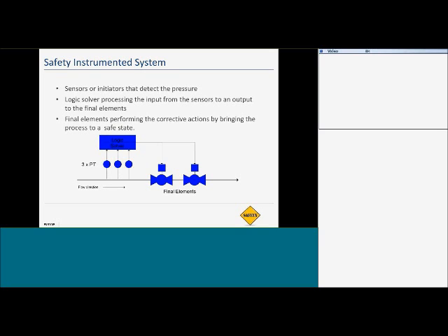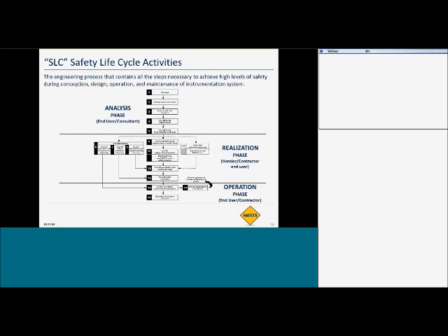So once again, just a little review, taking a look at what a safety instrumented system is. These are the components that are part of the SIF: the sensors, the logic solver, and the final elements. Now, the safety life cycle is another term that you'll hear frequently in discussions with your SIS engineer, and this is simply all of the processes from the very beginning of conceptual design, engineering, specifications, all of the realization phase, validating, planning, through commissioning and startup, and all the way through to eventually decommissioning. Another way they term this is cradle to grave. So the safety life cycle really starts right at the beginning of engineering design and goes all the way through to the decommissioning of the equipment.